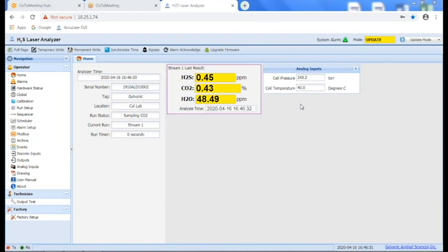So these two items here have alarms associated with them. If the cell pressure gets too high or too low, that can indicate issues with either the pump or the sample flow. For example, if the probe gets plugged and there's no flow to the analyzer, the pump will pull the cell pressure down, so you get a cell pressure low alarm. If something went wrong with the pump or the vent line became obstructed, you would get a high pressure alarm.